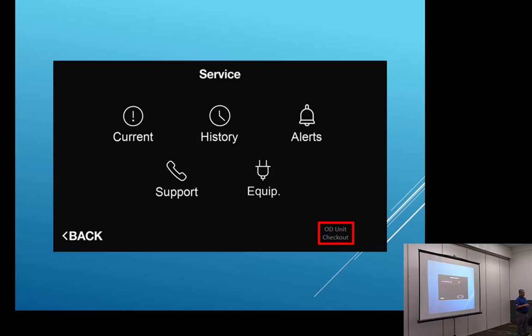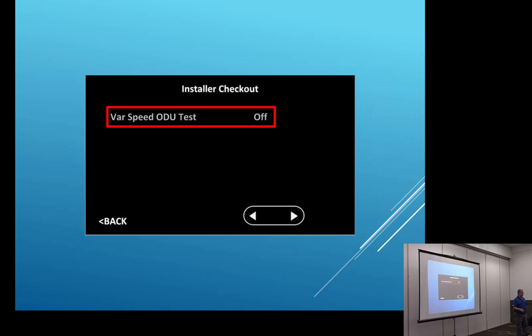Outdoor unit checkout. If you come into here, anytime we put our gauges on an inverter-driven piece of equipment, we need to have it in charge mode because that inverter is sitting there doing this. It's just like a drill, right? It's up and down, varying the speed. If we don't lock it in, we don't know. It's kind of like checking a unit that has a fan cycle switch outside. It comes on and then it goes off. The pressures are up and down. Same kind of thing, okay? So we need to lock it into one speed so we can check those pressures and charge it correctly. Okay?